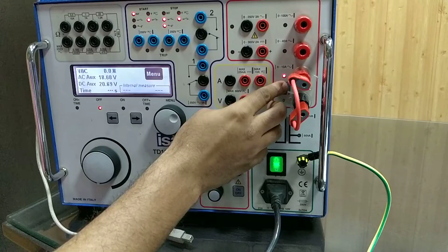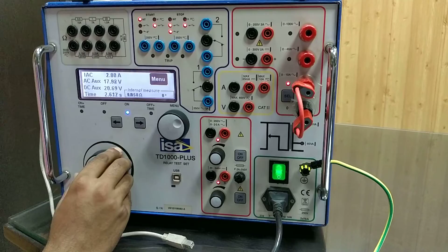We are selecting the current, and now we are generating current, and you can see on the screen we are generating 2 ampere current, 17 volt auxiliary AC, and based on this we are getting the impedance value as 8 ohms and 0 degree, because the phase angle between the auxiliary AC voltage and the current output is 0 right now. We have to generate the additional current source from the auxiliary AC voltage.